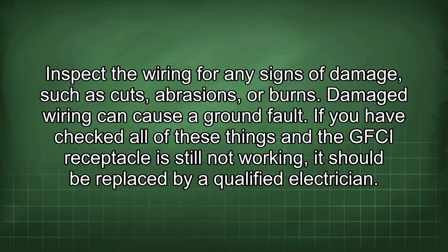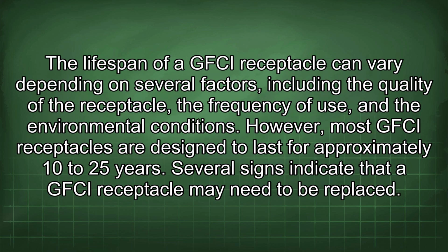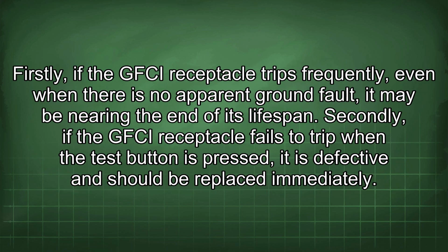by a qualified electrician. The lifespan of a GFCI receptacle can vary depending on several factors, including the quality of the receptacle, the frequency of use, and the environmental conditions. However, most GFCI receptacles are designed to last for approximately 10 to 25 years. Several signs indicate that a GFCI receptacle may need to be replaced.